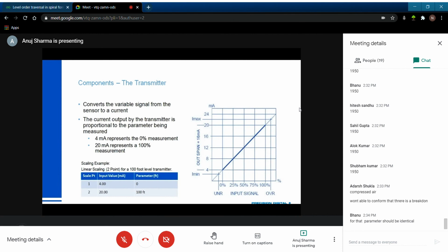So if I'm looking at the scaling example shown here, I would have a level transmitter that's designed for 100 feet. When I'm at 0 feet, my level transmitter is going to be outputting 4 milliamps. When it's detecting 100 feet, it's going to be outputting 20 milliamps. And then it just connects all the points in between. So if I'm at 50 feet in this tank that I have this transmitter on, it's going to be outputting a 12 milliamp signal.